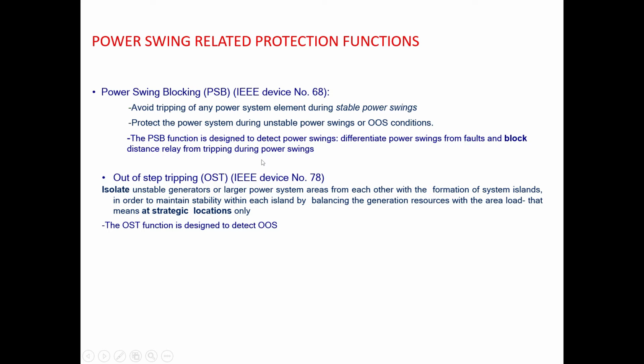The power swing function is designed to detect power swings, differentiate power swings from faults, and block the distance relay from tripping during power swing. This I have already explained. And out of step tripping, this also I have already explained.